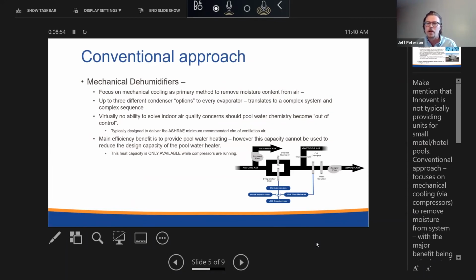Really, it was a focus on satisfying the dehumidification load through mechanical cooling, right? You dehumidify the pool air by running it through a cooling coil. Then you've got to reheat it, or you can reject the heat to an air-cooled condenser, or, and this is really the major benefit of the conventional mechanical dehumidifier approach, you can take that heat of rejection from the refrigeration process, and you can re-inject that back into the pool water. So that's kind of the flagship energy efficiency benefit of a mechanical dehumidifier. They say, well, hey, you've got this energy that you don't want to throw away. Why don't you reduce the heating load required on your pool water heater by taking it off the HVAC equipment? And it is an efficient solution.